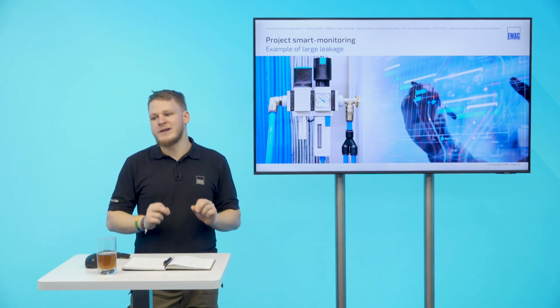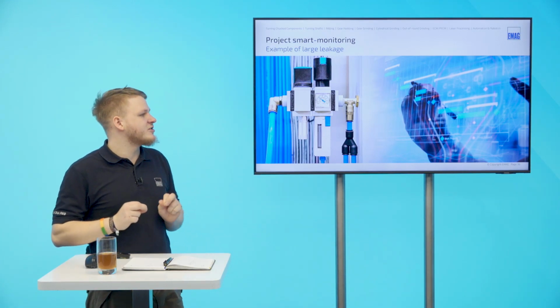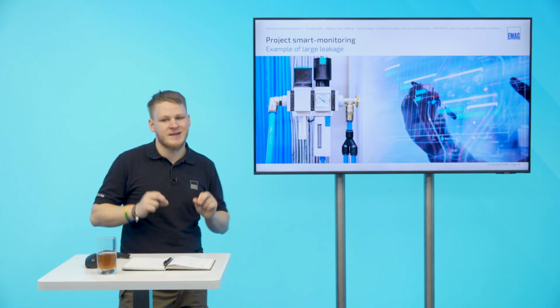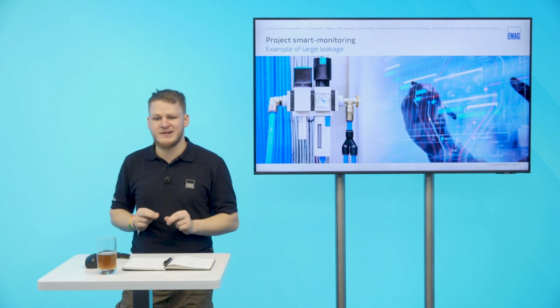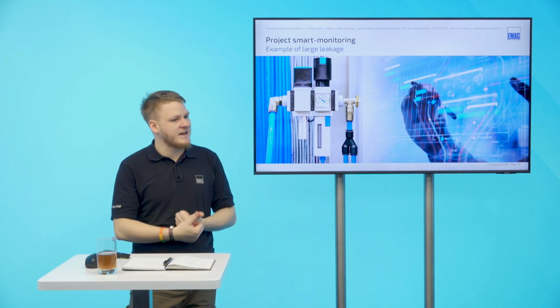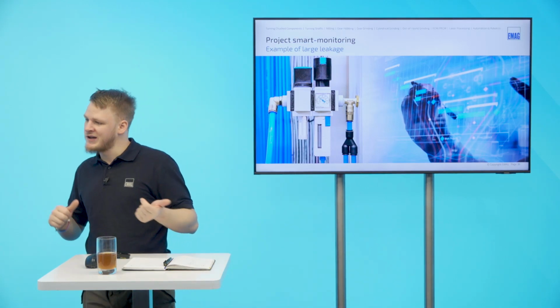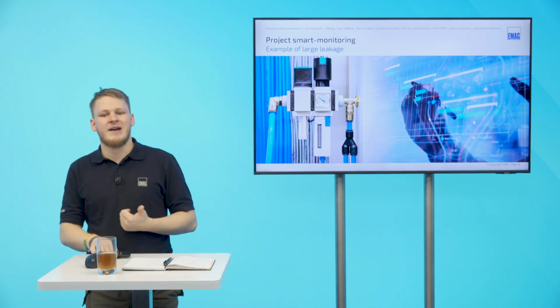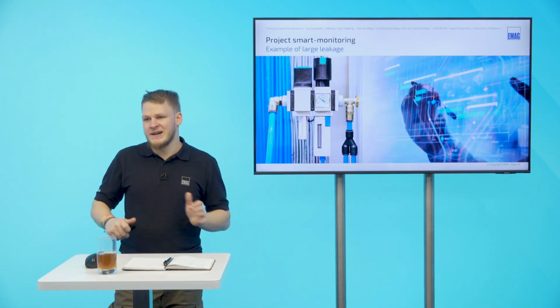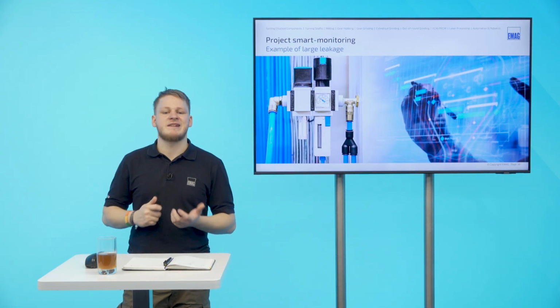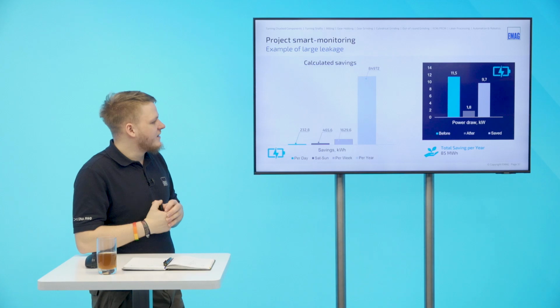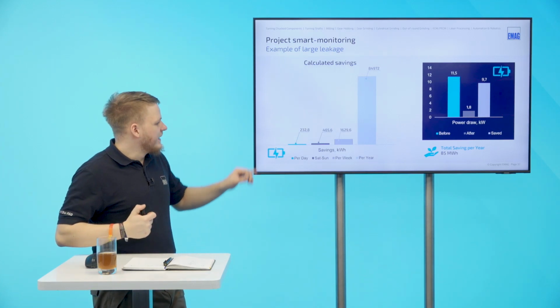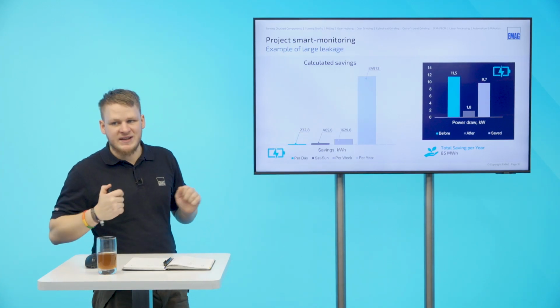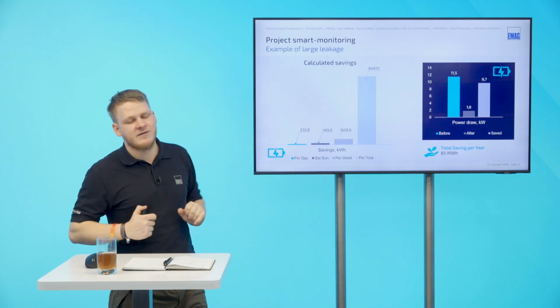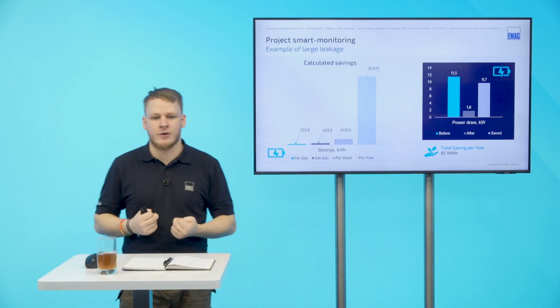That one hose had a total energy loss of 9.7 kilowatts permanently, meaning 365 days a year, 24 hours round the clock, during shifts and outside of shifts, which is a pretty significant amount. Just to see how significant, let's look at kilowatt hours: even on a day-to-day basis, each day we wasted 232 kilowatt hours.